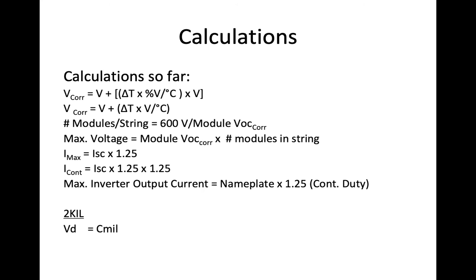Imax is short circuit current times 1.25. I continuous is short circuit current times 1.25 multiplied by another 1.25. Max inverter output current is nameplate rating of the continuous output and current times 1.25 for continuous duty. And now you have this last equation, which is 2KIL Vd equals Cmils.